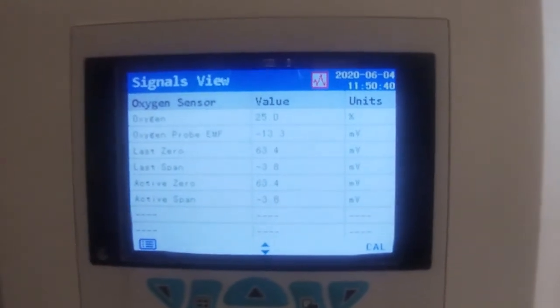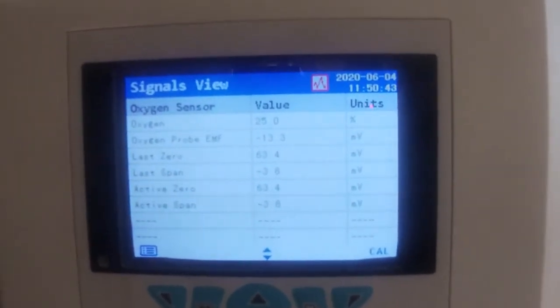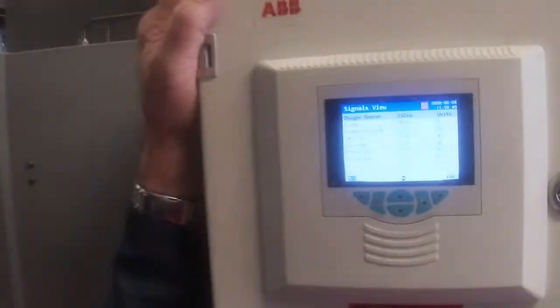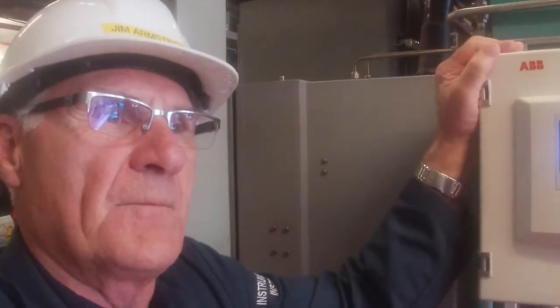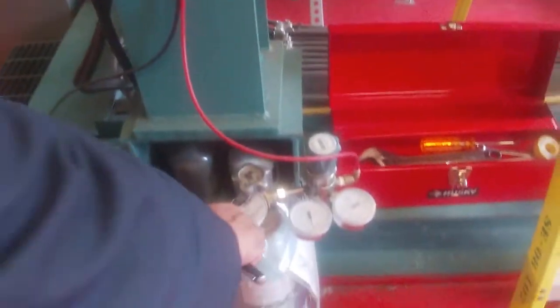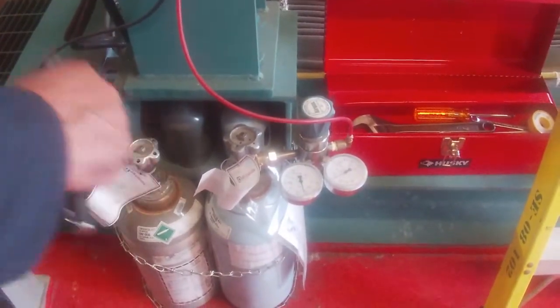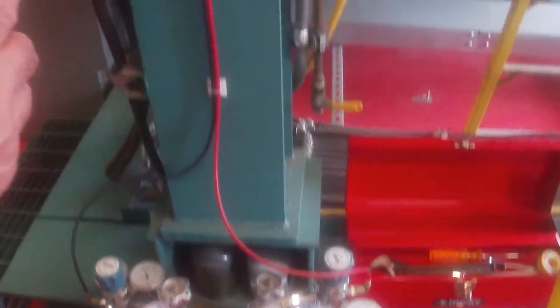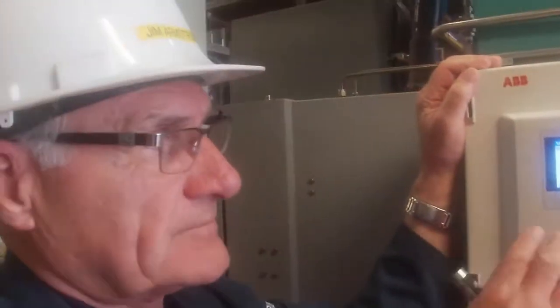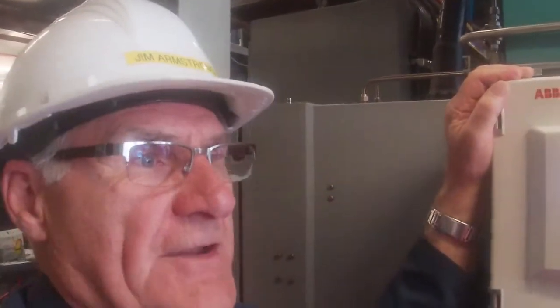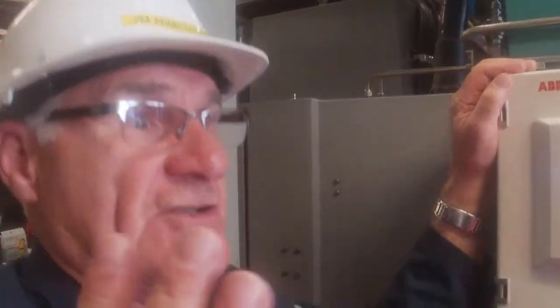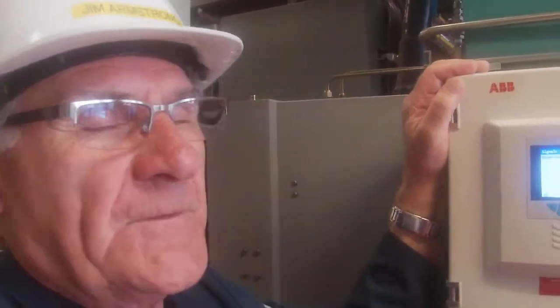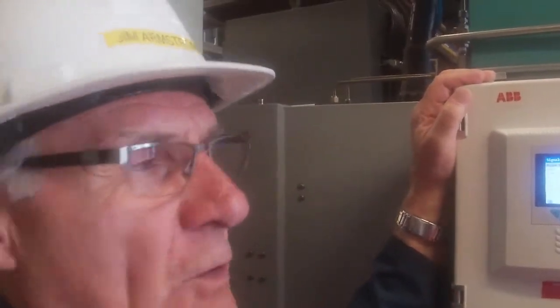This is a significant advantage over the analyzers that they previously had, where this guy remembers what your last good values were. And one of the problems you can get into is that if your gas bottles, which if we just look down here, I've got gas bottles down below me. This is my zero gas bottle and my span gas bottle. Well, if one of those bottles goes empty, then what can happen is that you'll be in the middle of a calibration and all of a sudden it's got no gas, and your calibration will be wrecked. If you don't have a replacement bottle, you are in deep trouble, and this was typical of the older analyzers.